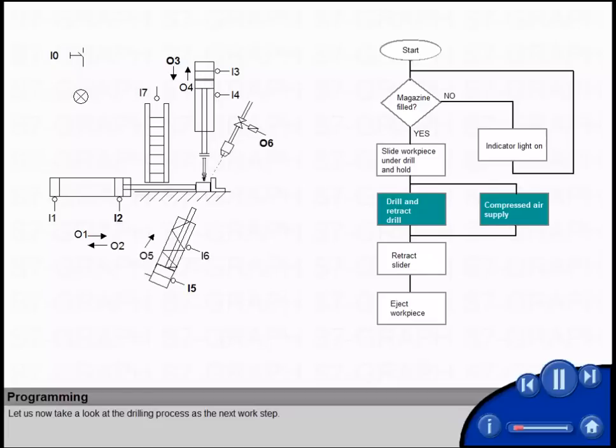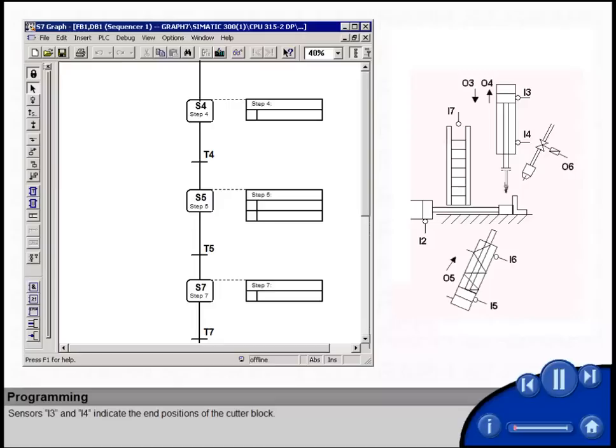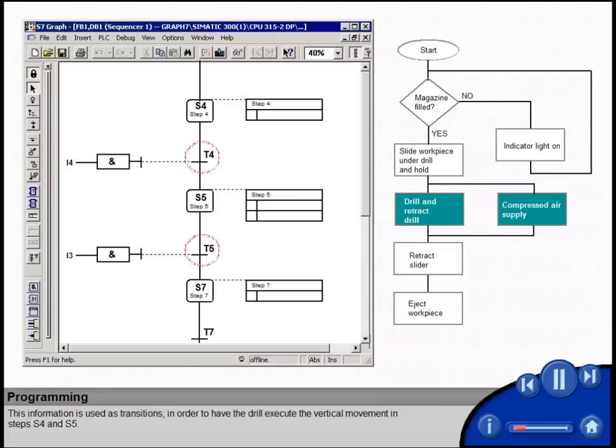Let us now take a look at the drilling process as the next work step. Here we will meet a simultaneous branch, at which both chain parts are processed, as it were in parallel. Sensors I3 and I4 indicate the end positions of the cutter block. This information is used as transitions, in order to have the drill execute the vertical movement in steps S4 and S5.